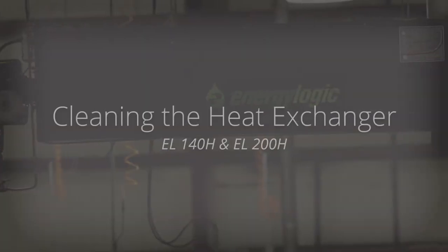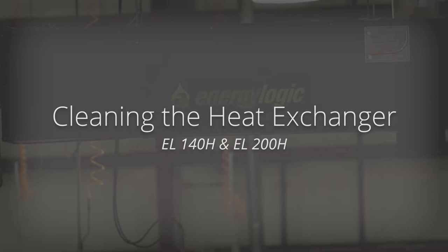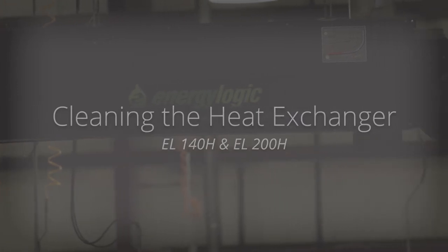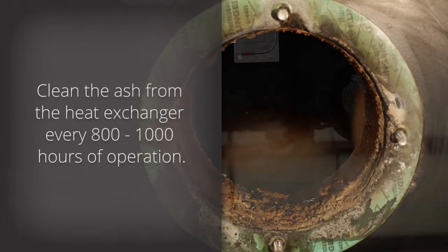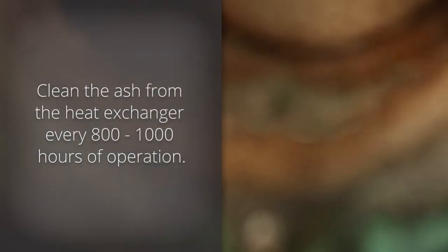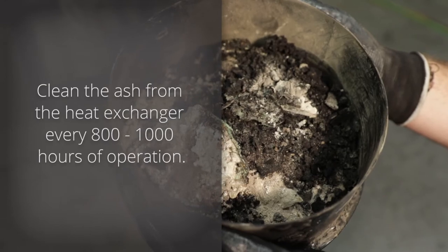This video will address the heat exchanger cleaning process for EnergyLogic 140H and 200H waste oil furnaces. You'll need to clean the ash from the heat exchanger every 800 to 1000 hours of operation. That's about once per year or twice for cold climates.